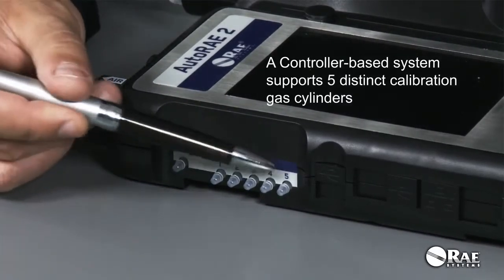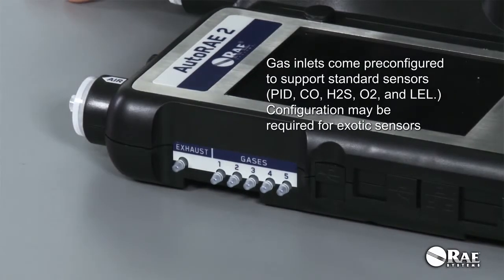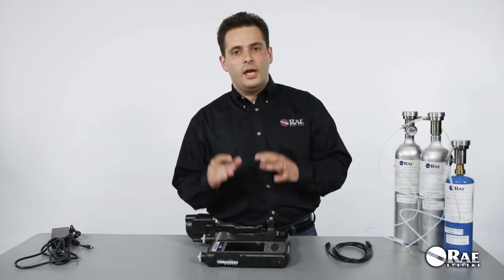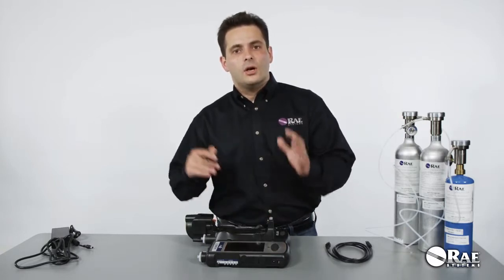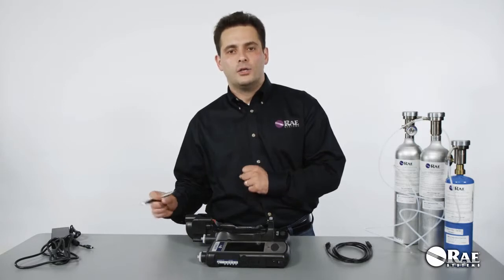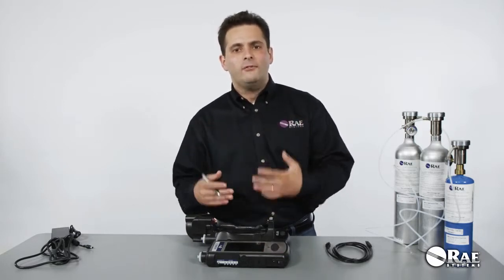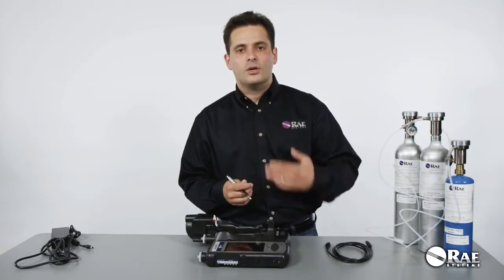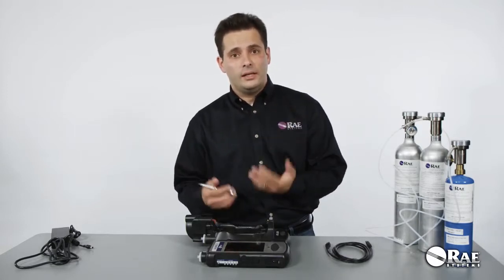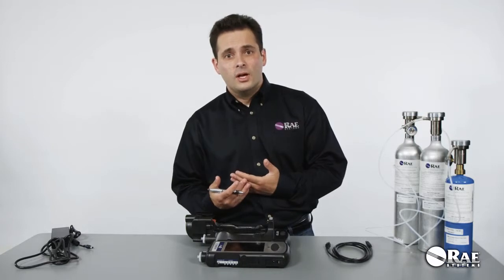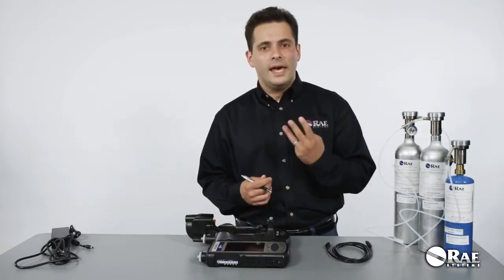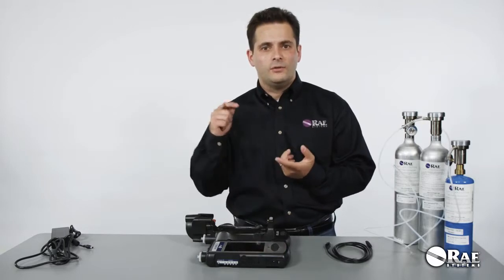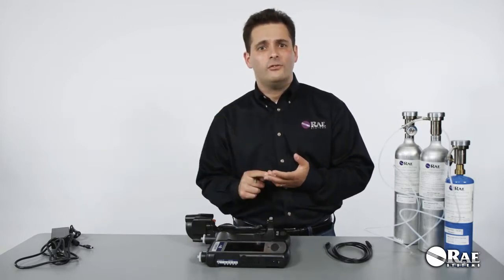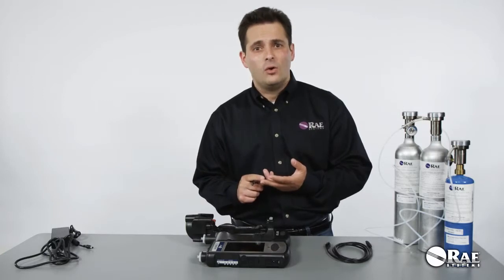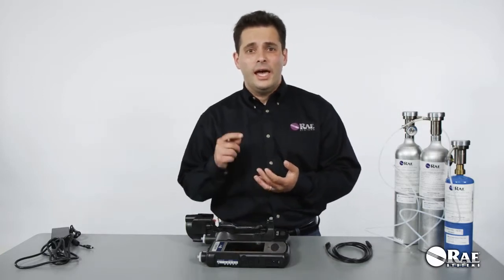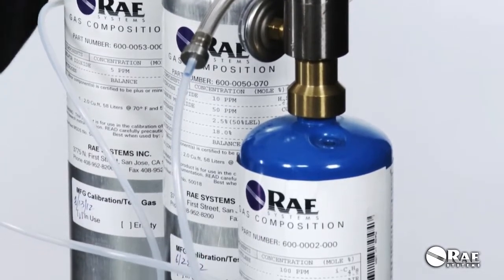So these 5 gas inlets are all configurable, and you need to make sure that they are configured in accordance with the sensor configuration on your MultiRAE. For example, if you have a MultiRAE that has a PID sensor, CO, H2S, O2, LEL, and SO2 sensors, you need to have at least the 3 following gases configured on your inlets. You have to have isobutylene for PID, you have to have a 4-gas mix for the CO, H2S, O2, and LEL sensors, and you have to have sulfur dioxide for the SO2 sensor.